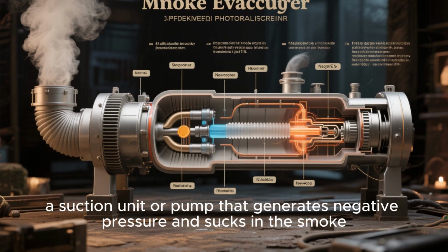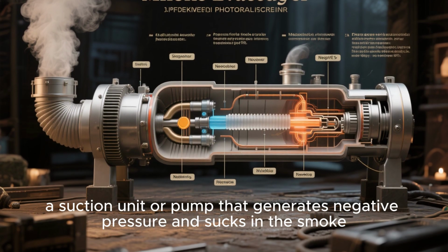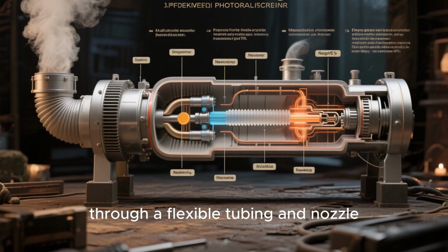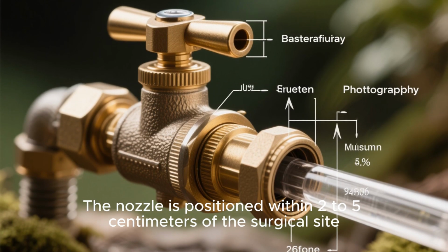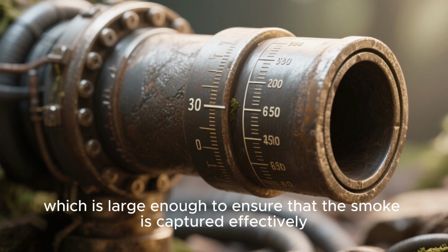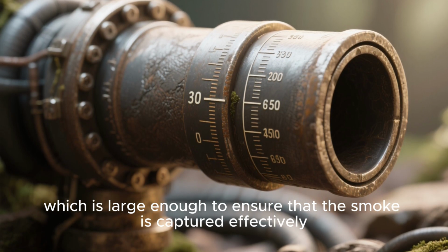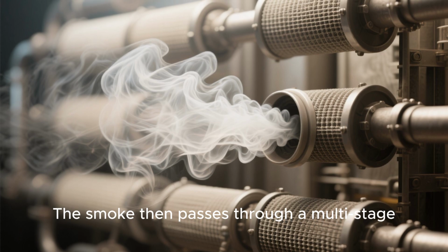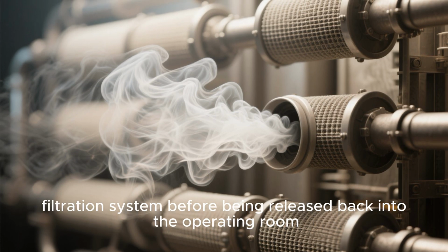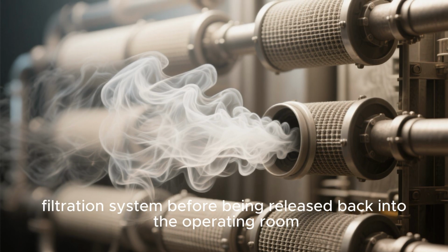How does it work? Well, the system works by having a suction unit or pump that generates negative pressure and sucks in the smoke through a flexible tubing and nozzle. The nozzle is positioned within 2 to 5 centimeters of the surgical site. The tubing has a diameter of about 7 to 10 millimeters, which is large enough to ensure that the smoke is captured effectively. The smoke then passes through a multi-stage filtration system before being released back into the operating room.